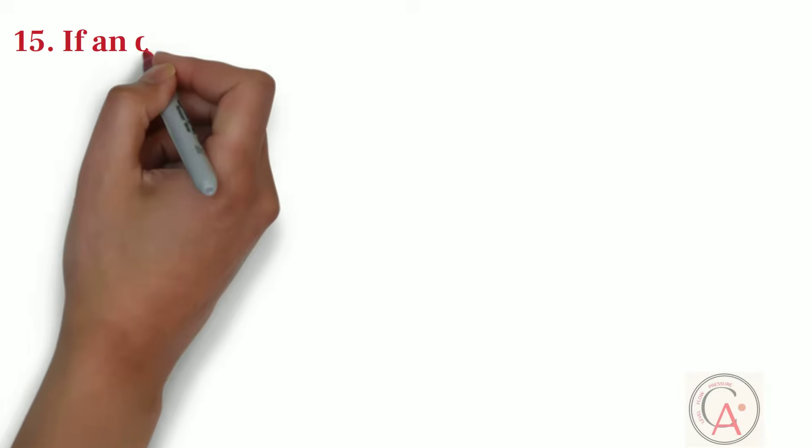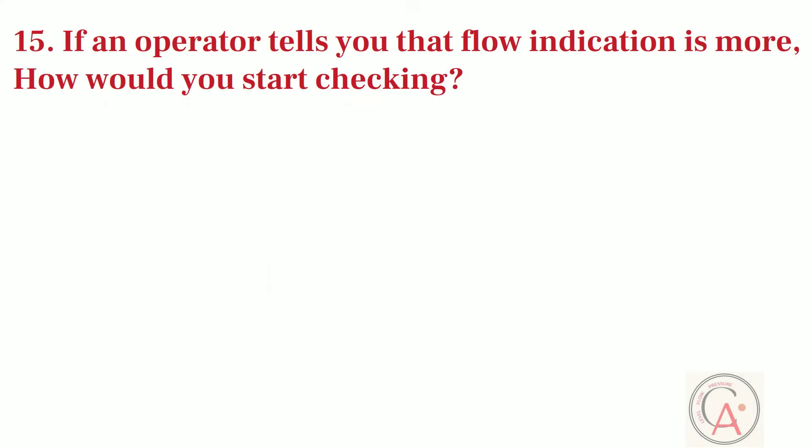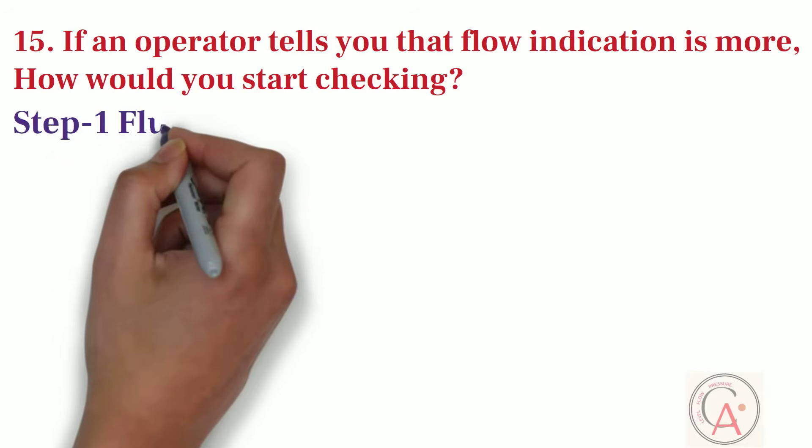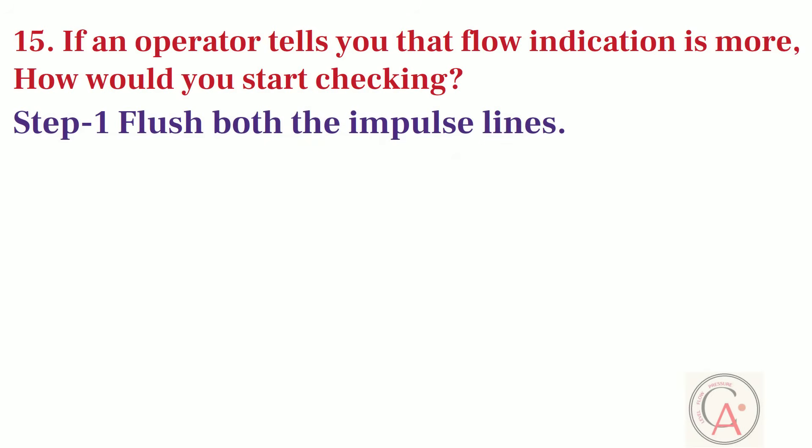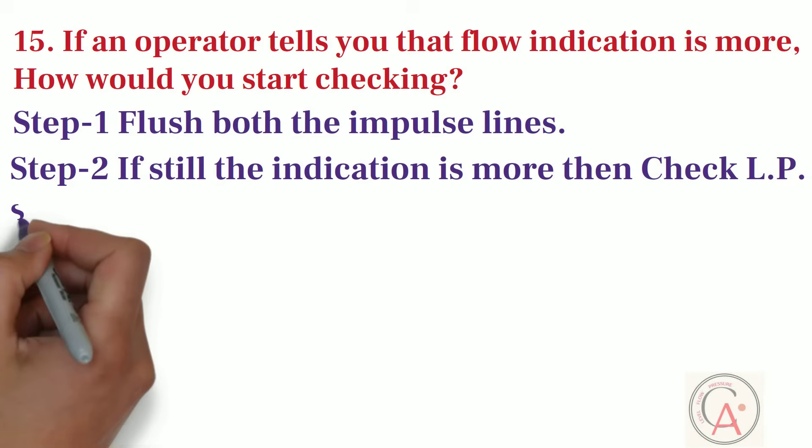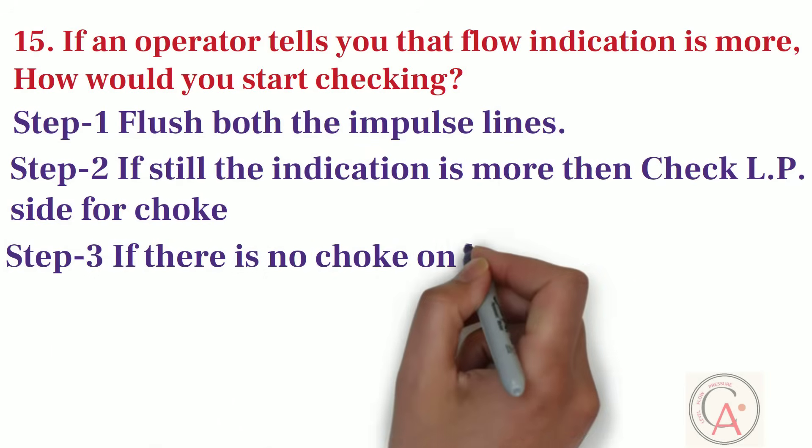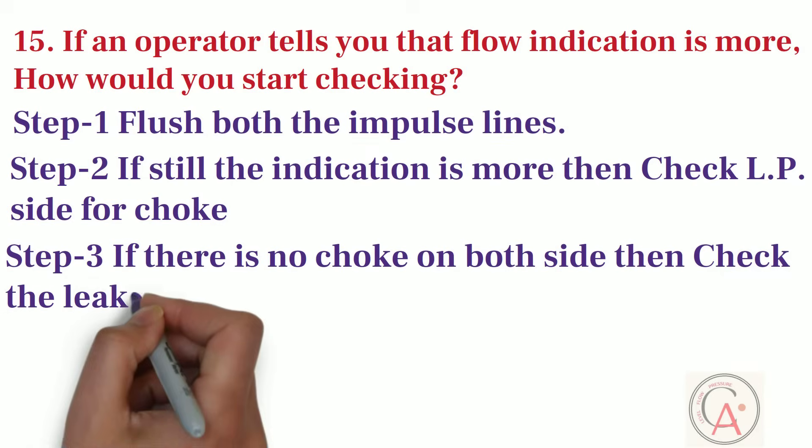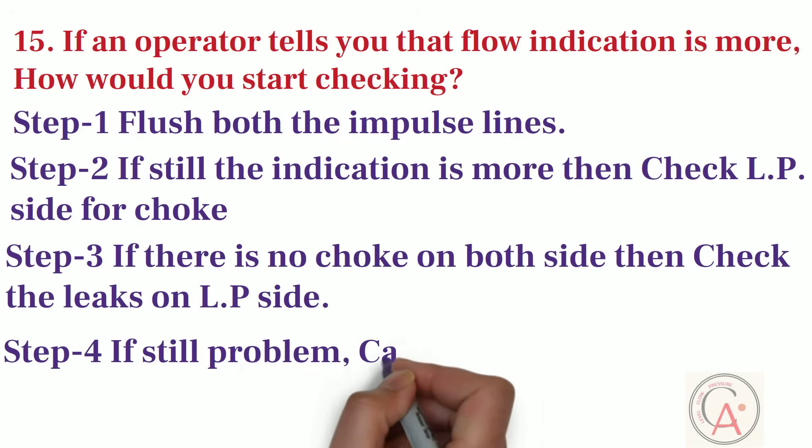Next question is, there is a situation when an operator tells you that flow indication is more than the expected reading, how would you start checking? First of all, in this case, flush both the impulse lines. Secondly, if still the indication is more, then check low pressure side for choke. If there is no choke on the both side, then check leaks on the LP side. If there is still problem, then calibrate the transmitter.